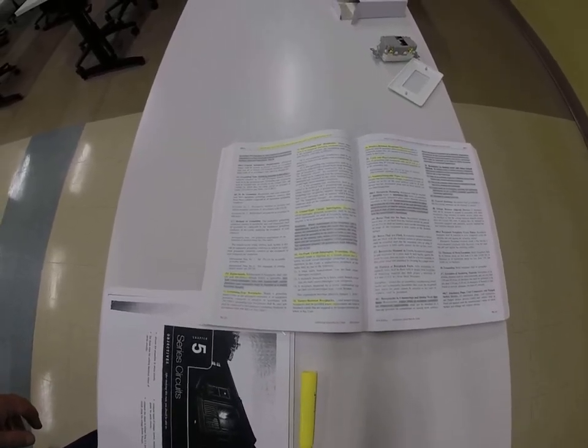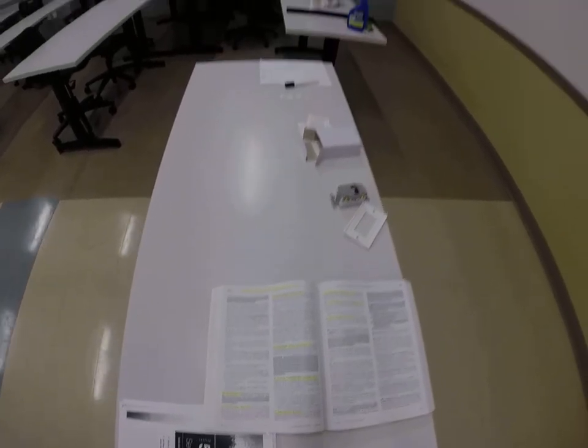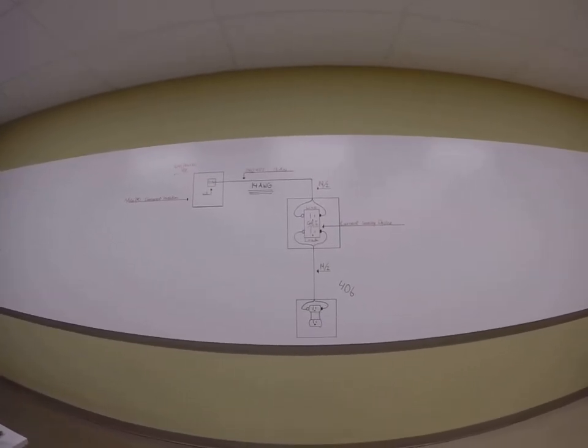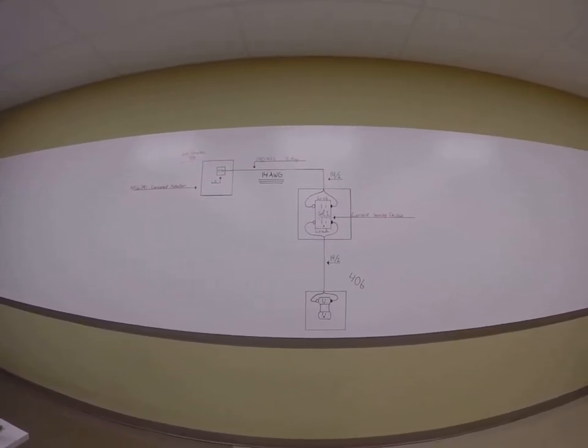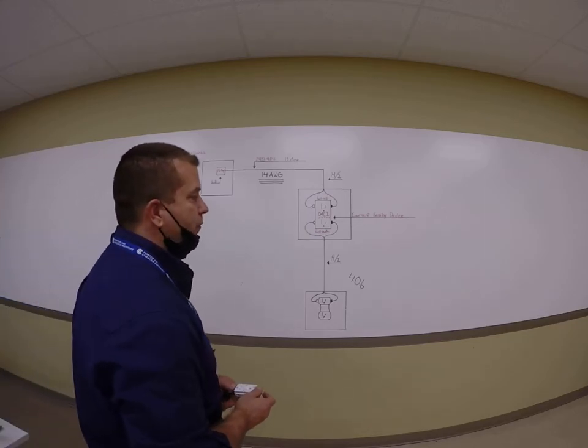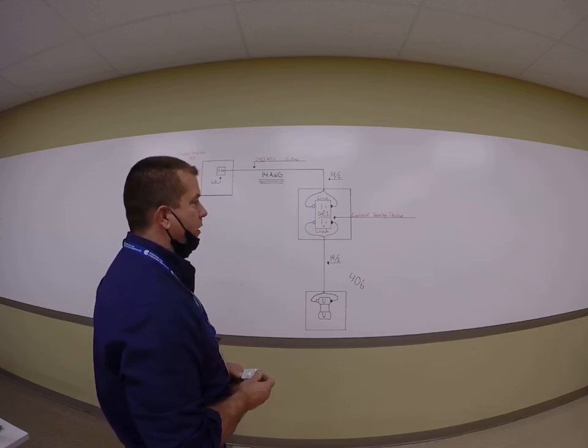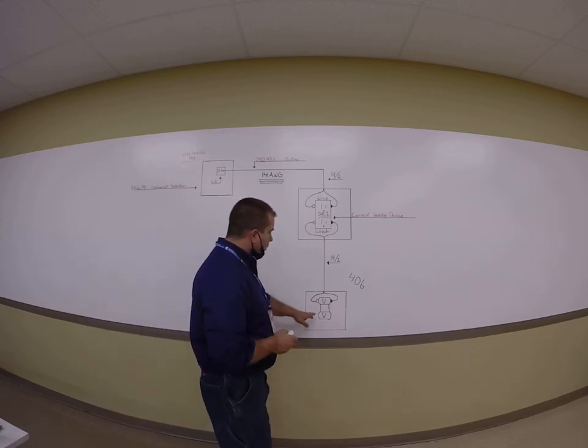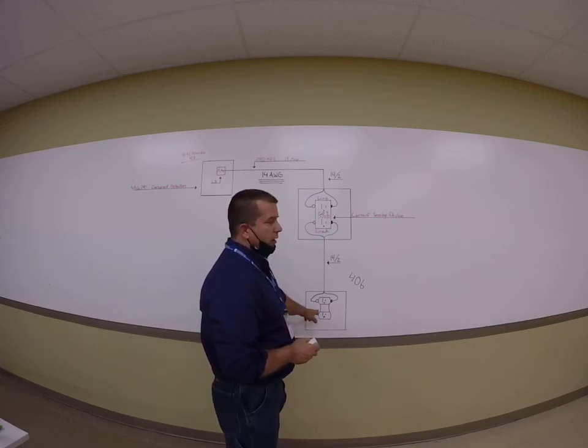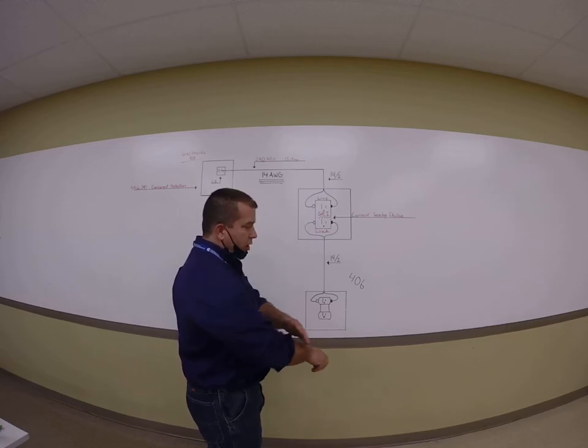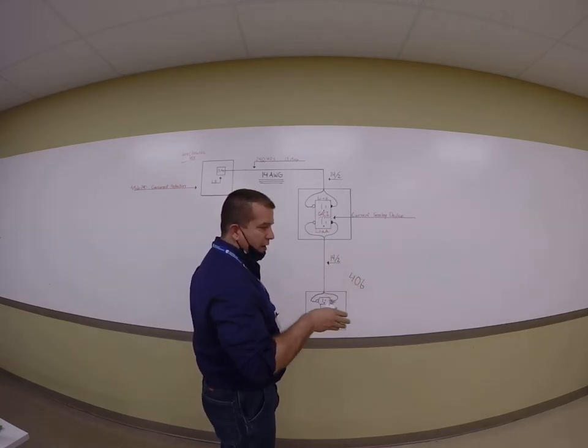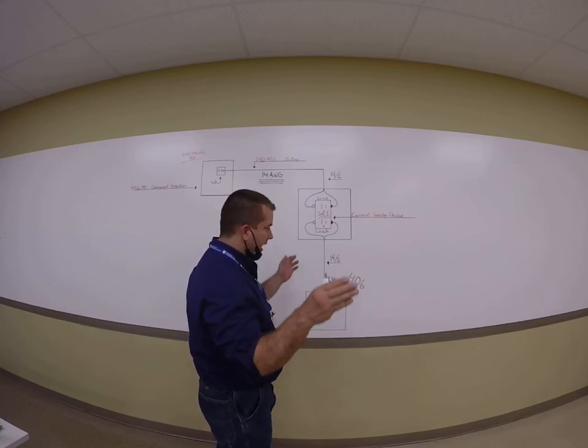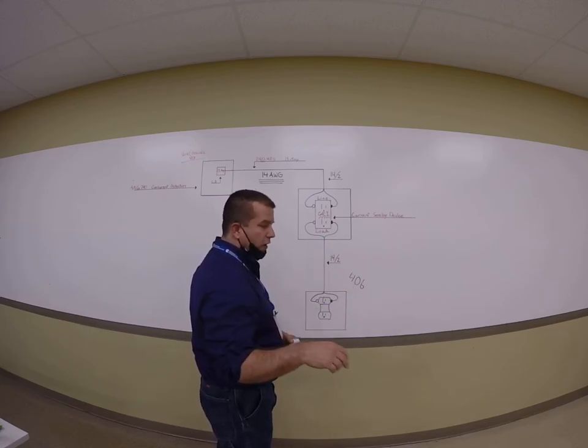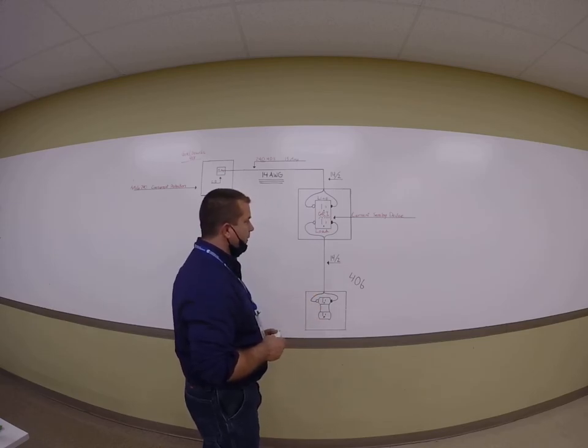It's probably a good idea to get this code in your head, whatever edition you're looking at, so that when you're out there making a little bit of side money for people, you take into account that tamper resistant receptacles, arc fault type receptacles, or GFCI receptacles are required to be put in many different areas in dwelling units. It's pretty rare when you're putting in a regular receptacle in a dwelling unit as a replacement, because you don't know what's behind the box until you take the receptacle off and see if there's an equipment grounding conductor in there. There's a lot of variables in the code that require you to know this stuff before you just start swapping out receptacles. But that's for another lesson.